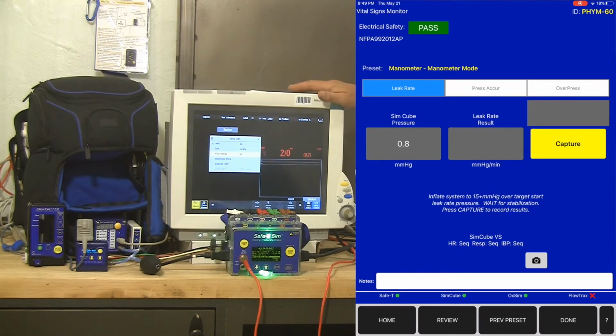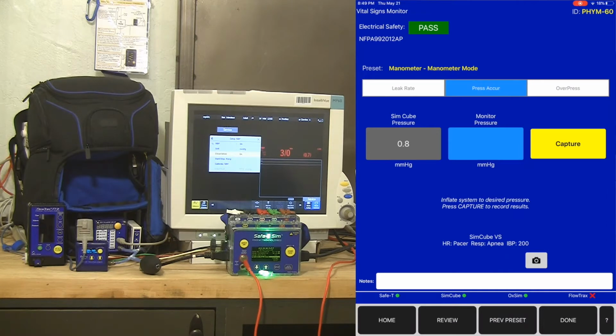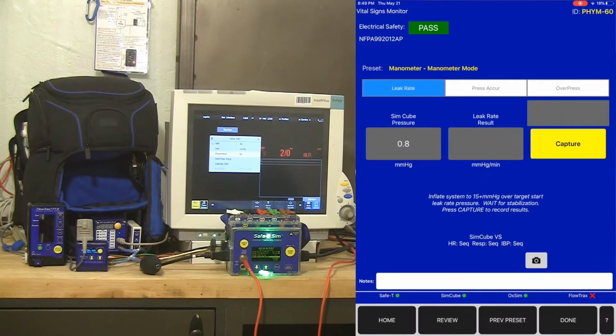So I've already got the monitor into service mode, and I've closed the valves. From our app, we've got 3 different selections in manometer mode. We've got leak rate, pressure accuracy, and overpressure. We're going to start with a leak rate.